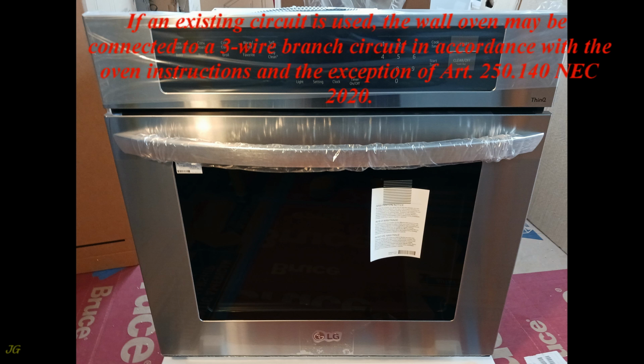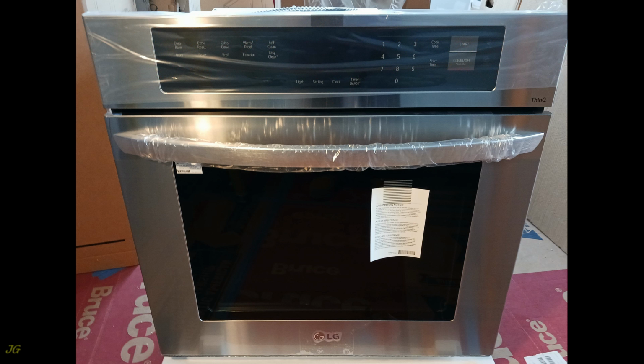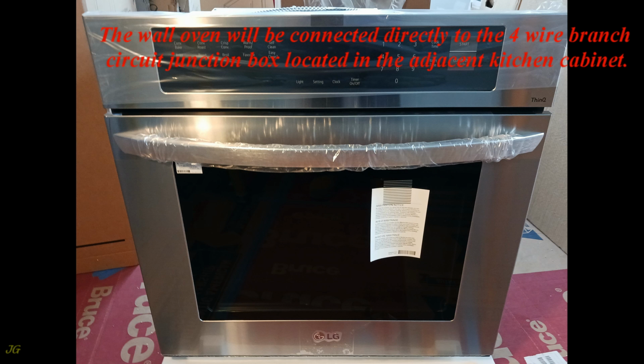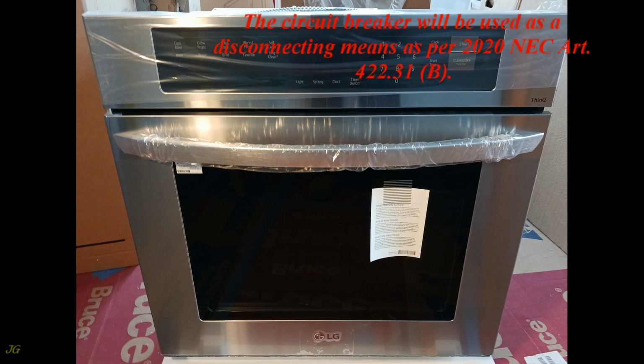If an existing circuit is used, the wall oven may be connected to a 3-wire branch circuit in accordance with the oven instructions and the exception of Article 250.140 NEC 2020. The wall oven will be connected directly to the 4-wire branch circuit junction box located in the adjacent kitchen cabinet. The circuit breaker will be used as a disconnecting means as per 2020 NEC Article 422.31 B.